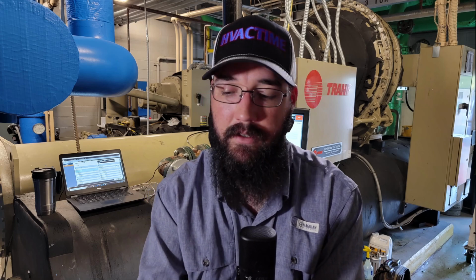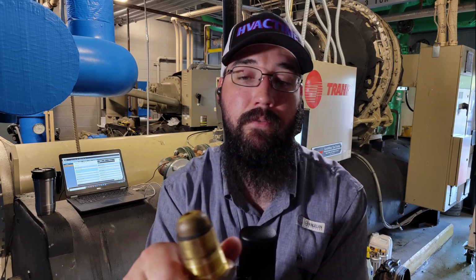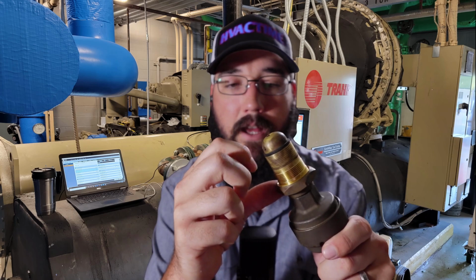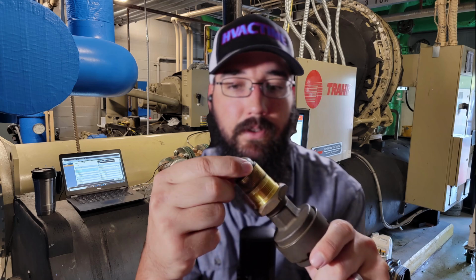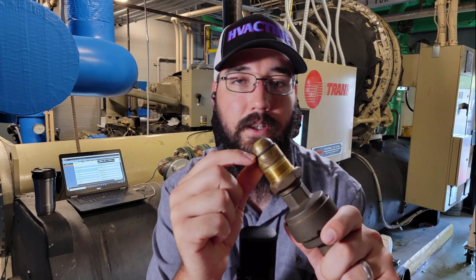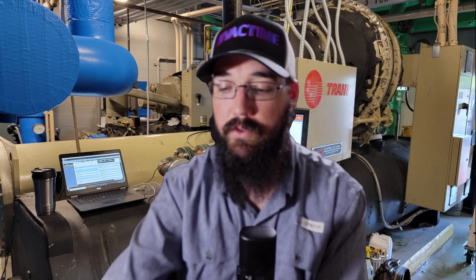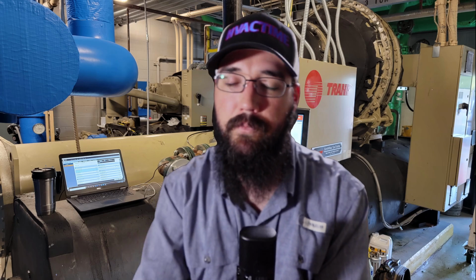I don't want to leave that in there while I'm trying to sweat and risk it getting messed up. One, the Teflon threads. Two, these will have rubber seals and such, which is what's sealing against the body to stop the refrigerant flow. Those things don't take heat very well.